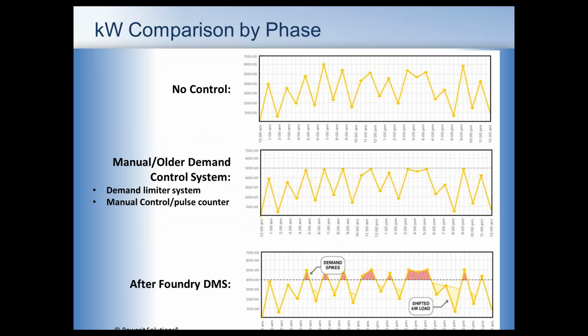So basically, this slide is somewhat of a comparison for what we achieved at Canon Muskegon Corporation. Initially, there was no control on the system, upper portion of the slide. You can see our set points were all over the place. We installed a step limiting control, and a lot of facilities out there have an old PLC where they look at a set point and they get some step control in there and they're able to control their power. But yet you still have lots of peaks and lots of areas where you can shave, but due to the interference that the step control contributes to the operation, you have to have an artificially high set point.